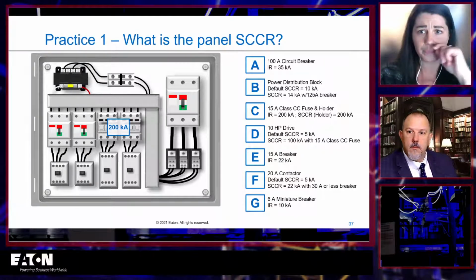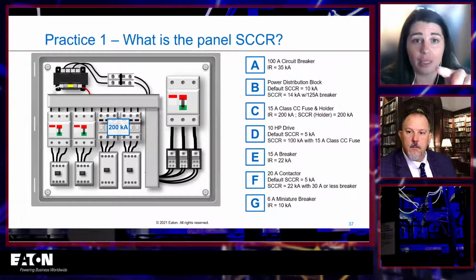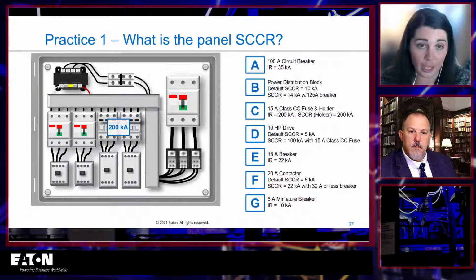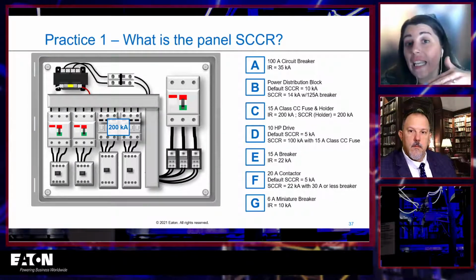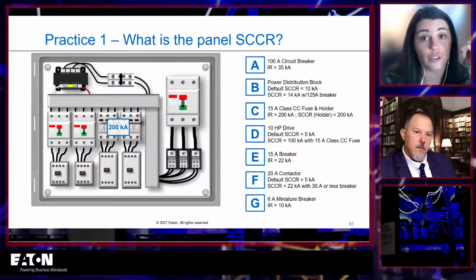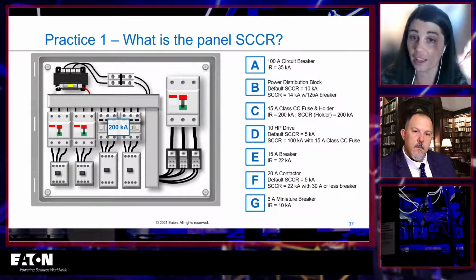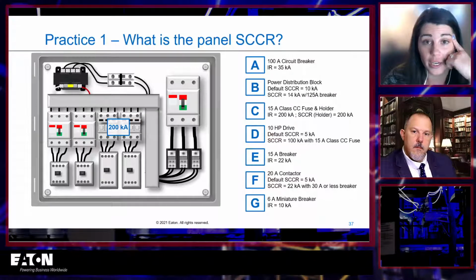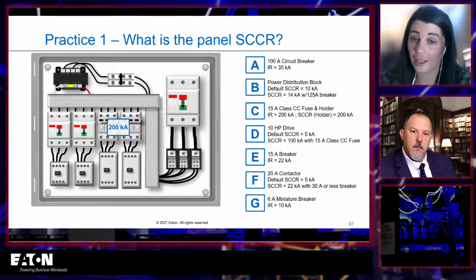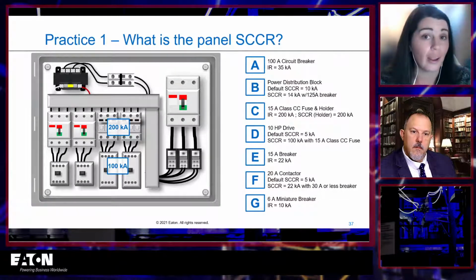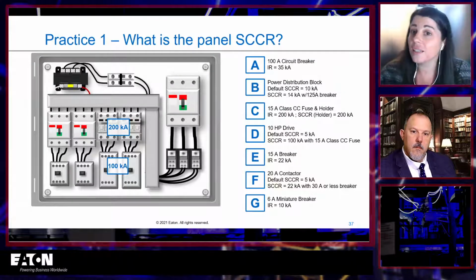My first one is branch CD, which is that fuse and fuse holder and that 10 horsepower drive. So we've got 15 amp Class CC fuses, interrupting rating 200 kA, and SCCR of the holder also 200. So we've put 200 kA right on there. Perfect. For D, we have a 10 horsepower drive. Its default short circuit current rating is 5 kA, but it has a high fault rating of 100 kA if I'm using 15 amp Class CC fuses in front of it. I am using 15 amp Class CC fuses in front of it. Therefore, its short circuit current rating is 100 kA.